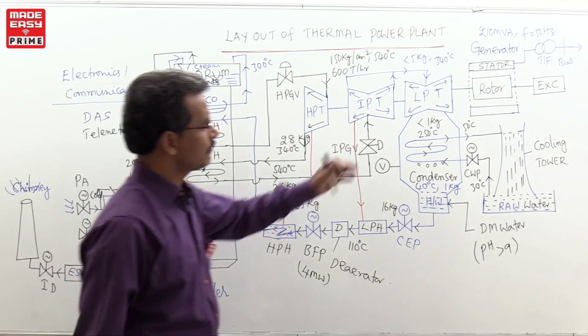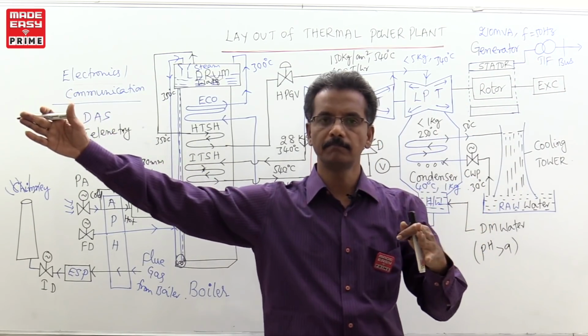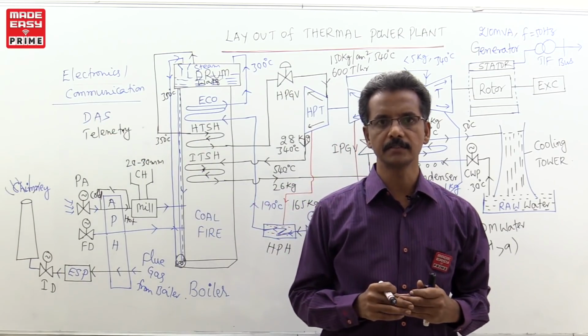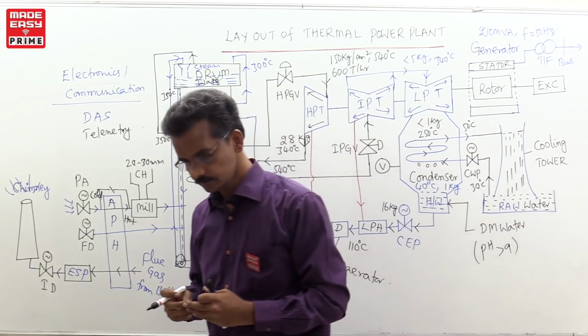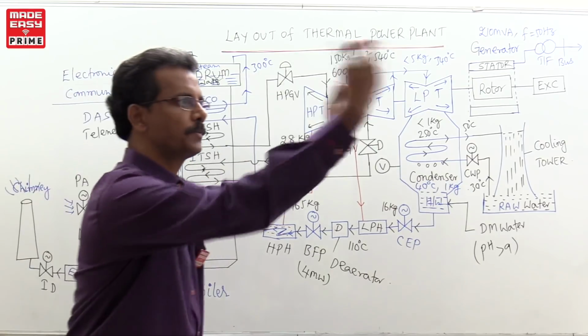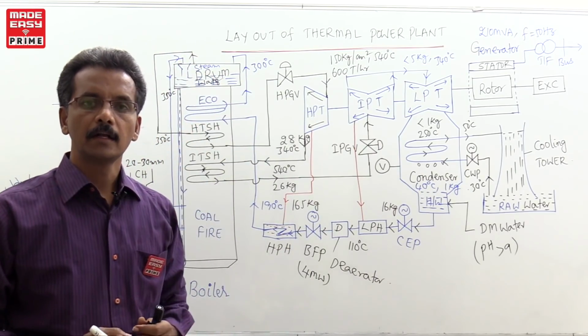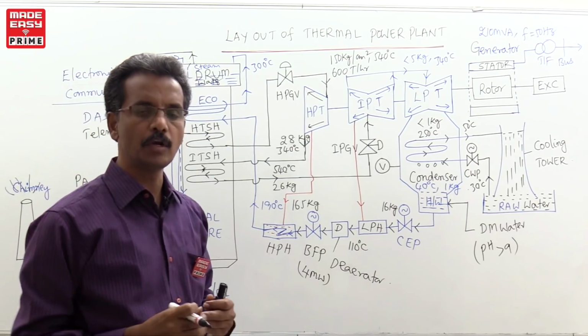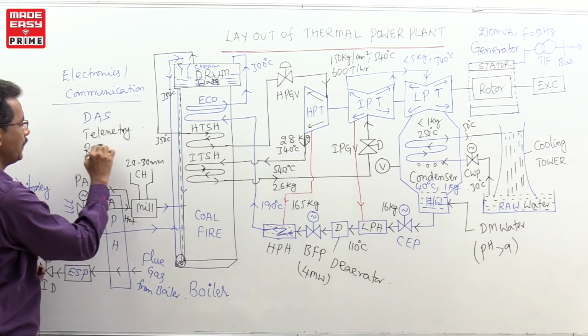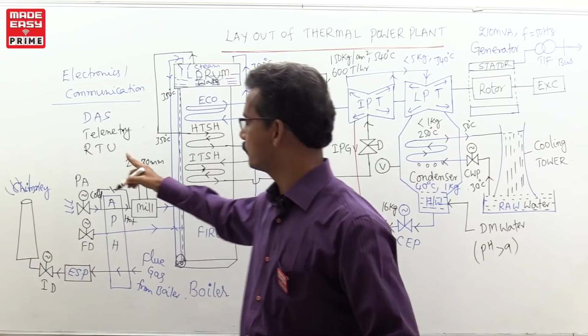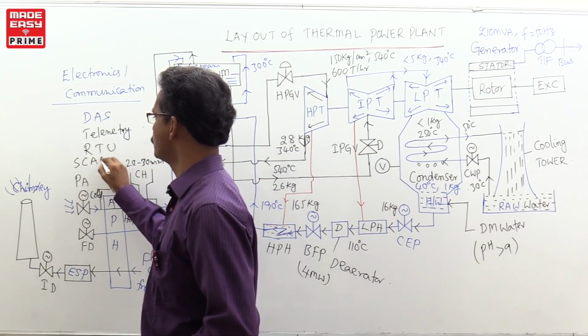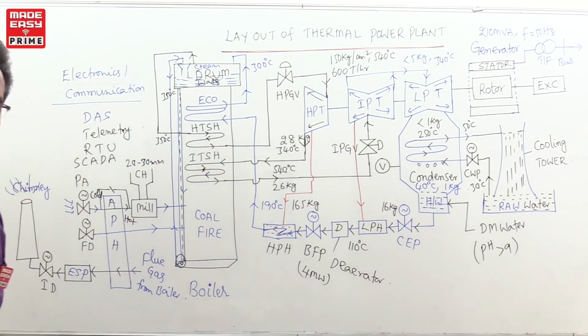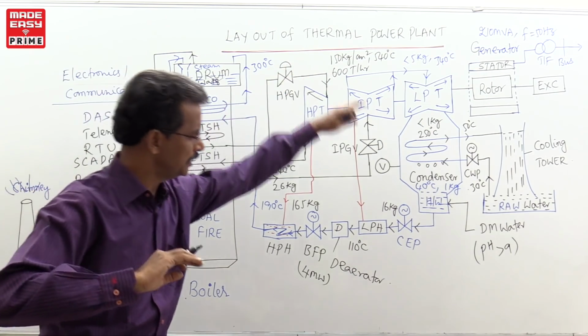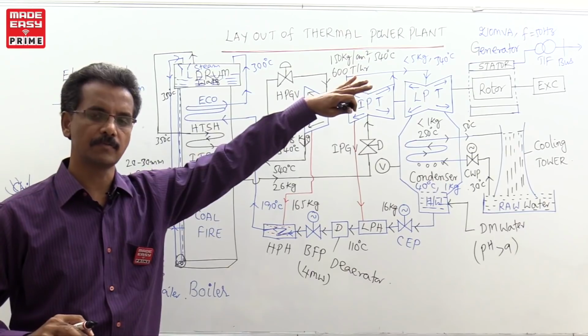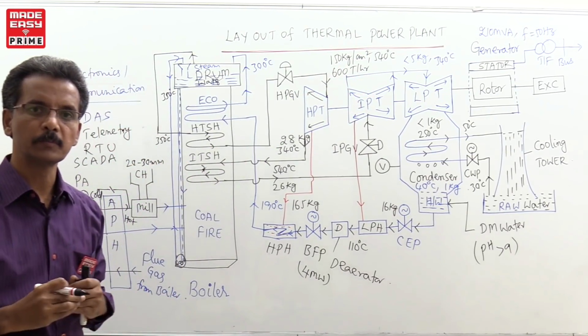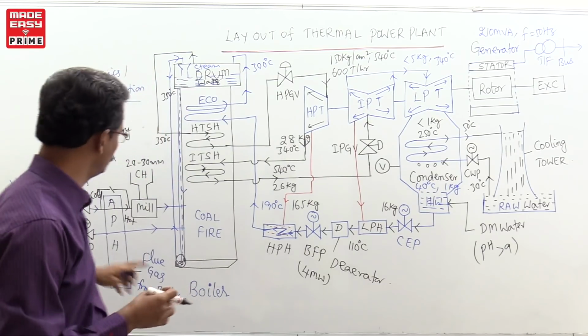One more thing, the power we are getting here is transmitted through the power lines at a frequency of 50 hertz. But how much power are we transmitting? How much voltage, how much current? These things are supposed to be transmitted to the main load dispatch center. For that, the communication people maintain remote terminal units. Many of you know this name. They use the SCADA technique, supervisory control and data acquisition. By using this method, they transmit the main parameters of generator and transformer data to the load dispatch center. That is the communication process using SCADA.